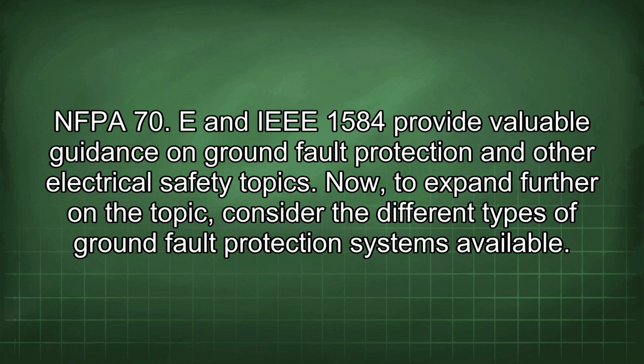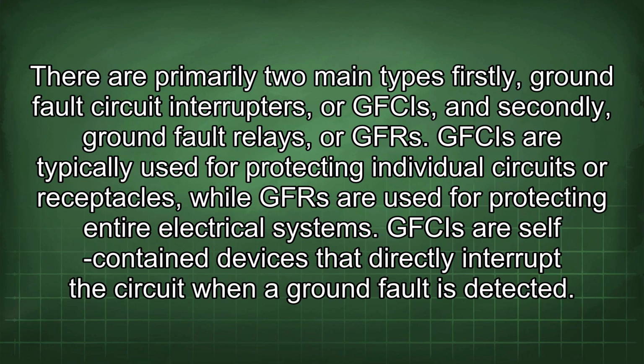Now, to expand further on the topic, consider the different types of ground fault protection systems available. There are primarily two main types: firstly, ground fault circuit interrupters, or GFCIs, and secondly, ground fault relays, or GFRs. GFCIs are typically used for protecting individual circuits or receptacles, while GFRs are used for protecting entire electrical systems. GFCIs are self-contained devices that directly interrupt the circuit when a ground fault is detected.